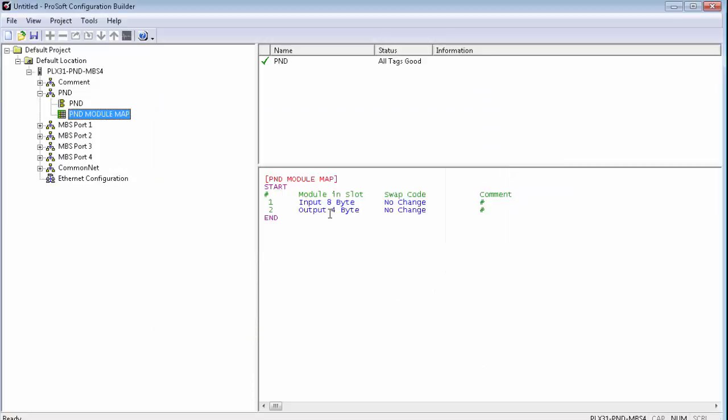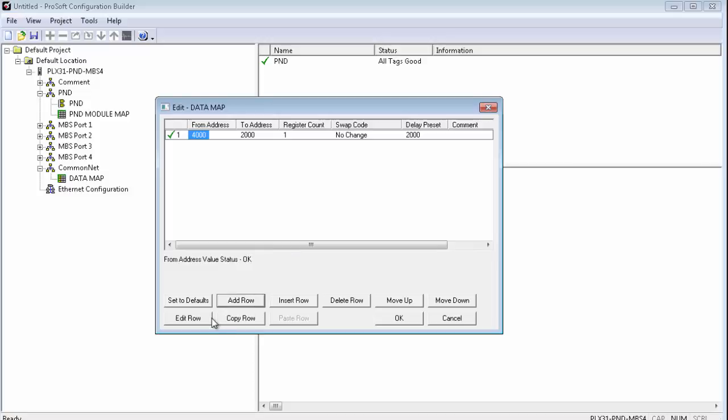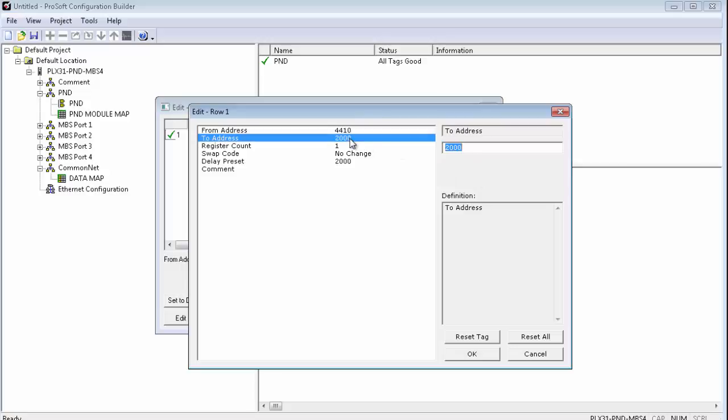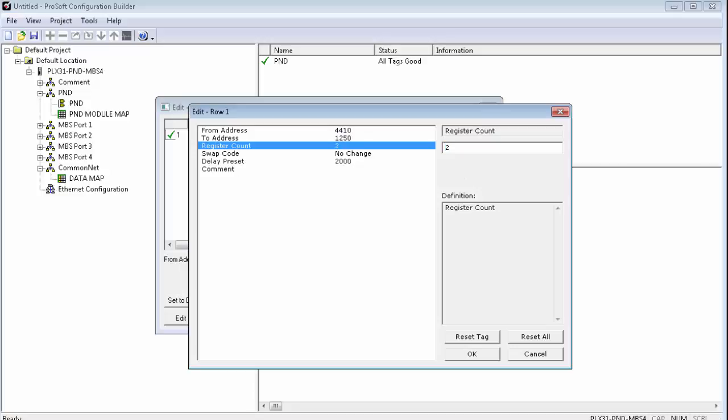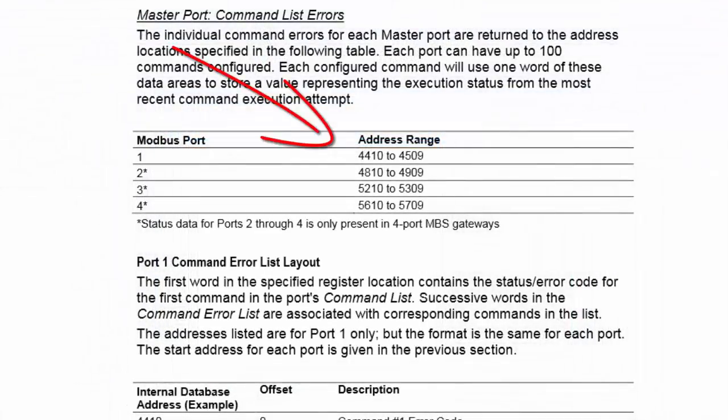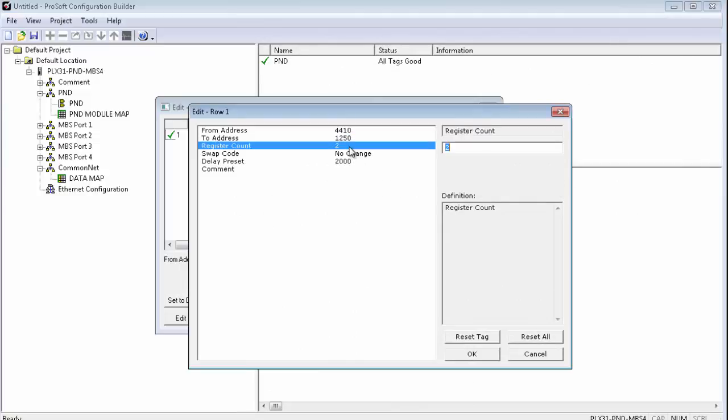To map in that status data that I referred to earlier, we just need to expand CommonNet then double-click on Data Map. Add a row and edit the row. The only status I'm concerned with is the state of the Modbus connections. So, we'll map in from address 4410 to address 1250 with a length of 2. 4410 is the start of the command error list for Modbus commands on port 1. And 1250 is a spot in our database that can be read by the PROFINET controller. By giving it a length of 2, this will let us know the status of the first two commands on port 1.